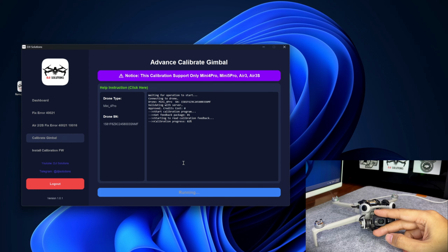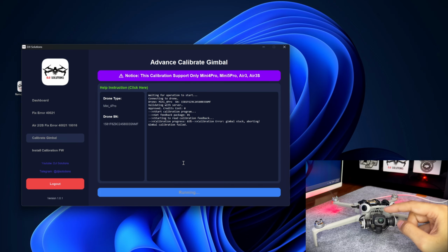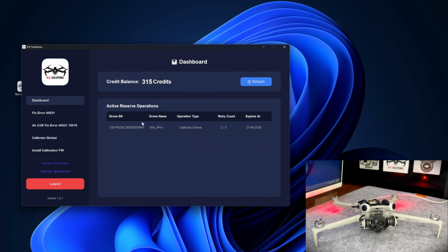What I'm going to do is physically block the gimbal from moving during the calibration process. If the gimbal can't move freely, the process will time out and fail. As expected, the process has failed. Now let's go back to the dashboard and check the active reserve section. You can see the retry count has increased by 1. We're now at 2 failed attempts on this operation. The serial number and operation type are clearly displayed, so everything is tracked properly.